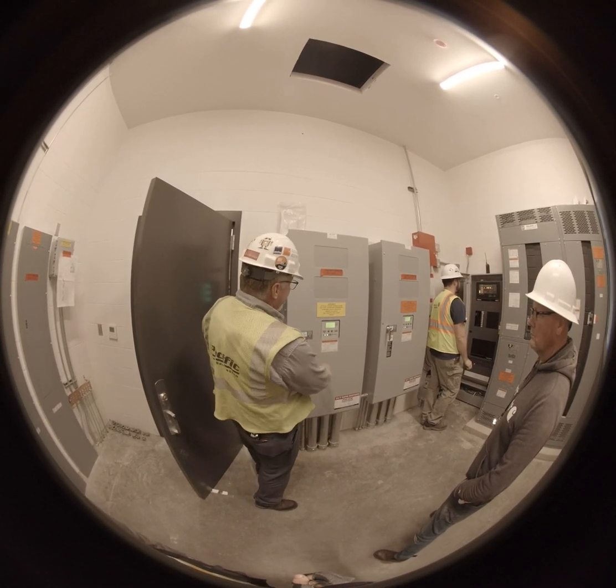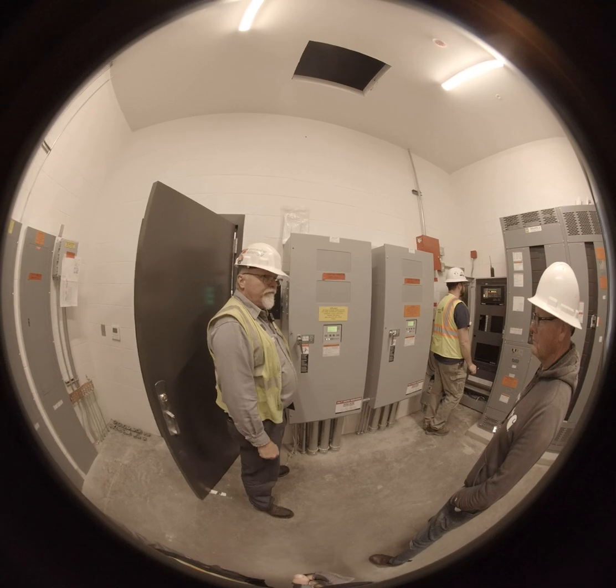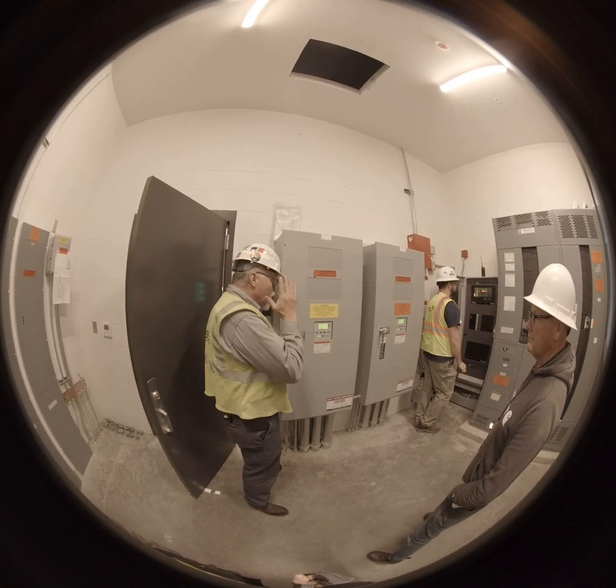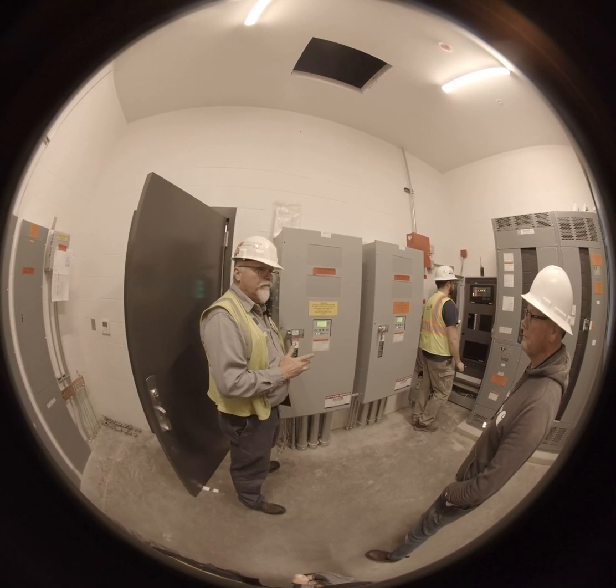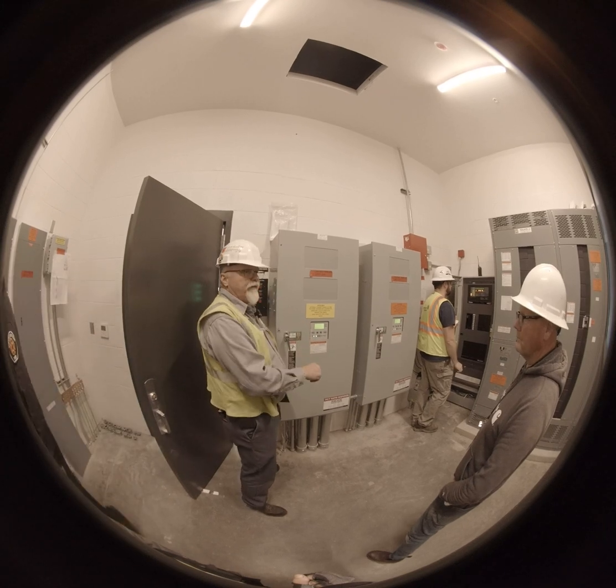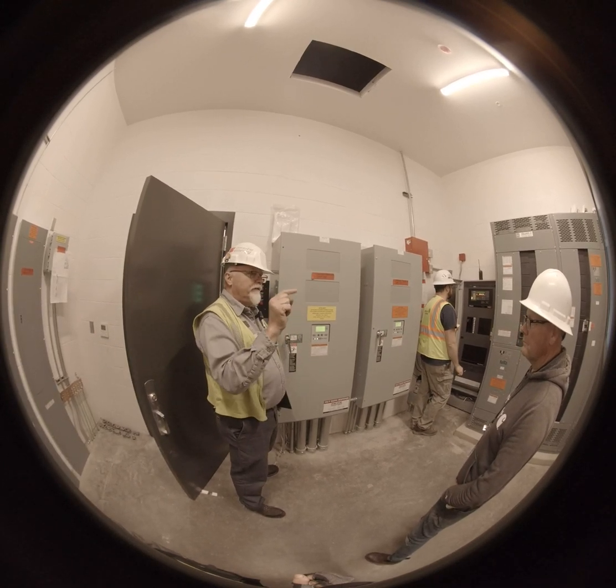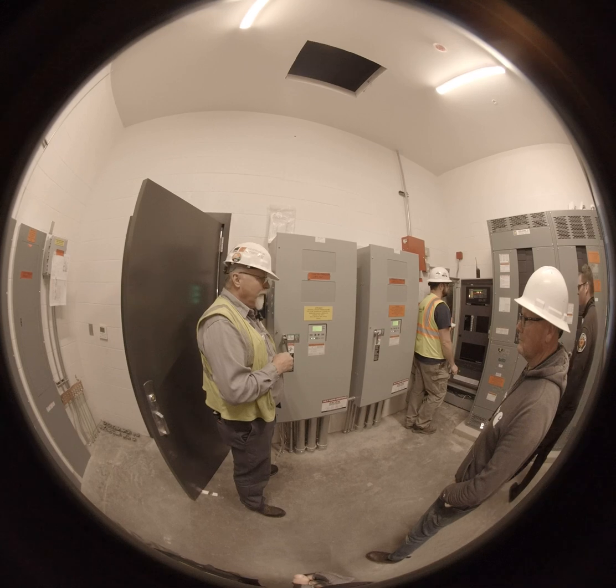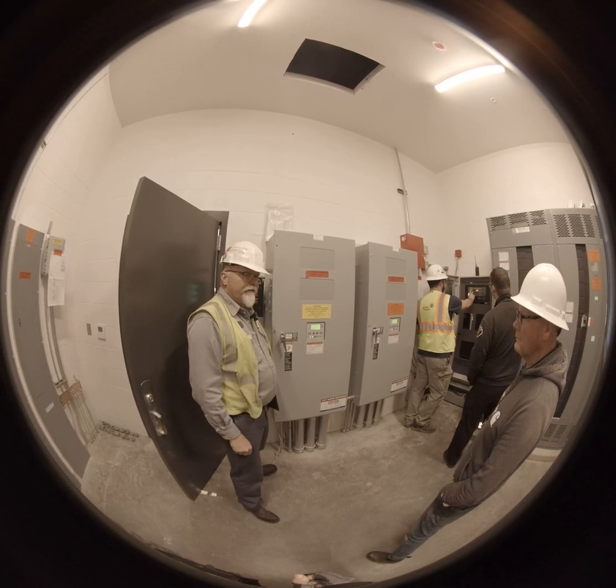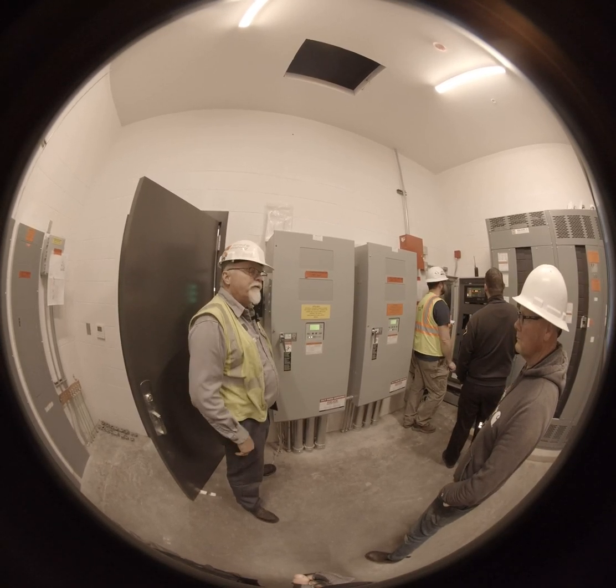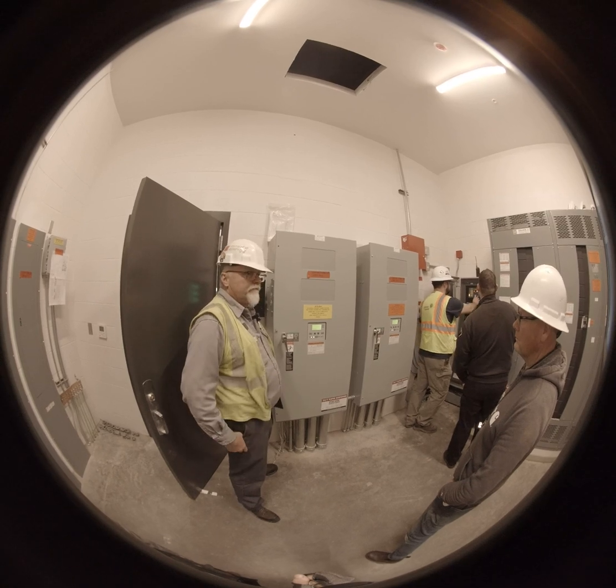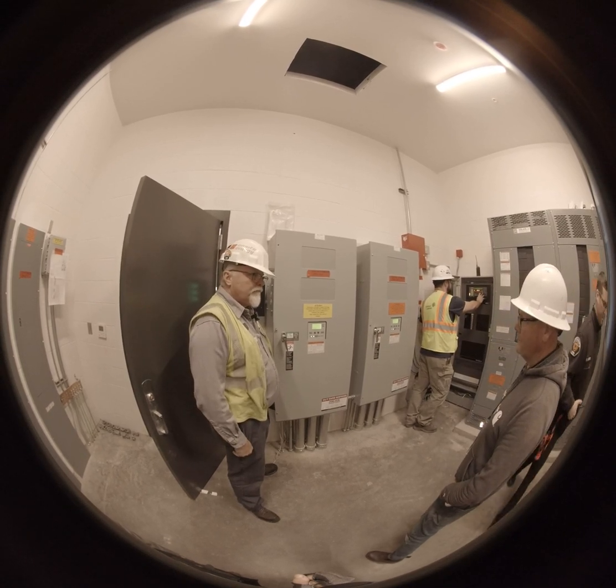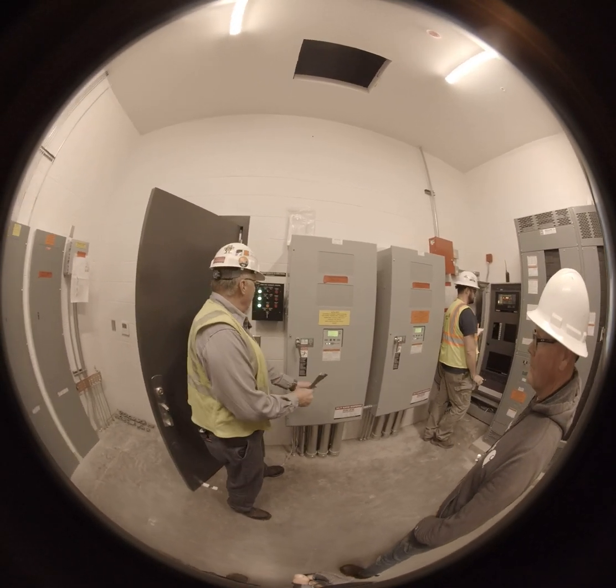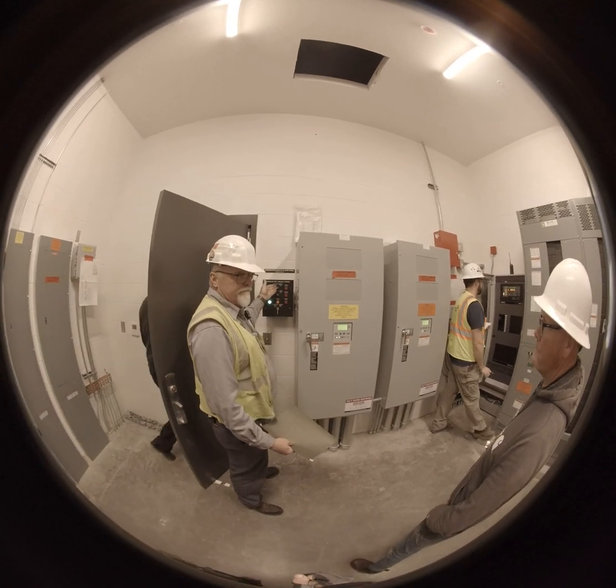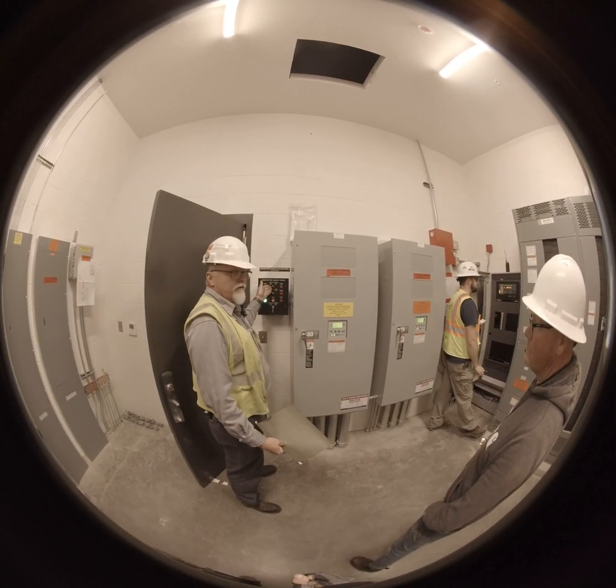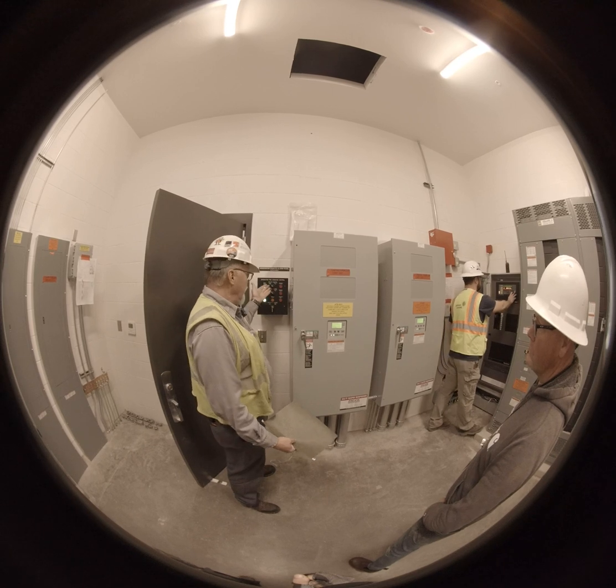The other operation is your push to test. For push to test, you have to enter that passcode also. So you're going to push it, it's going to come up, ding, ding, ding, ding, what you saw there, and then push it, and it'll fire up and transfer, run through its time delay, and then transfer back. Now, you have that same functionality right here. It's not intended for that. This is intended for the fire command, but you have that same functionality.